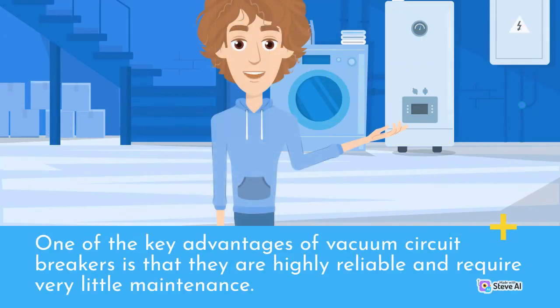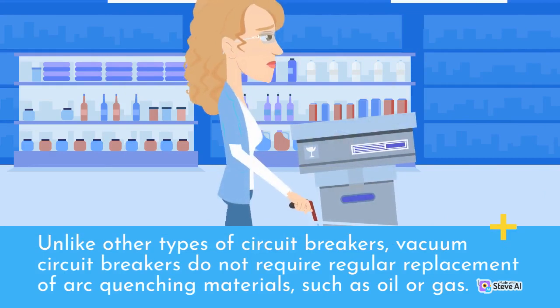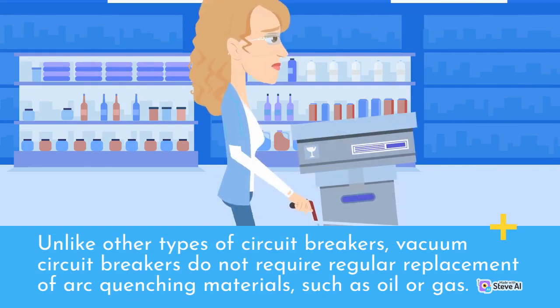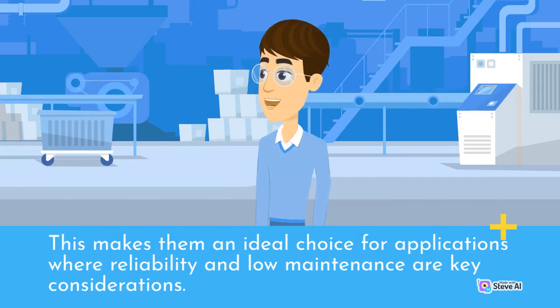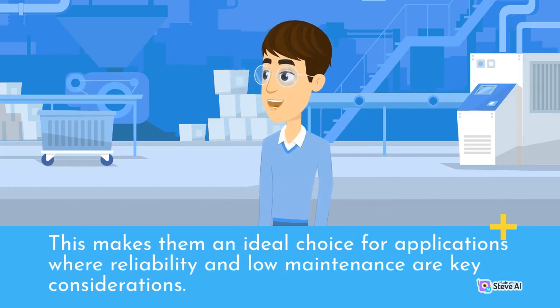One of the key advantages of vacuum circuit breakers is that they are highly reliable and require very little maintenance. Unlike other types of circuit breakers, vacuum circuit breakers do not require regular replacement of arc quenching materials, such as oil or gas. This makes them an ideal choice for applications where reliability and low maintenance are key considerations.